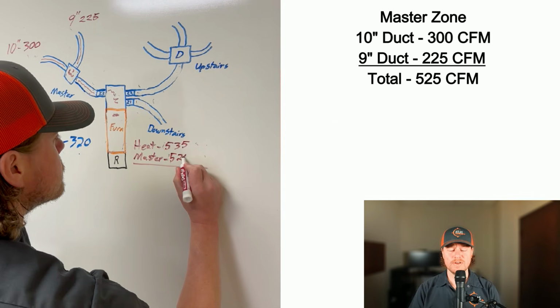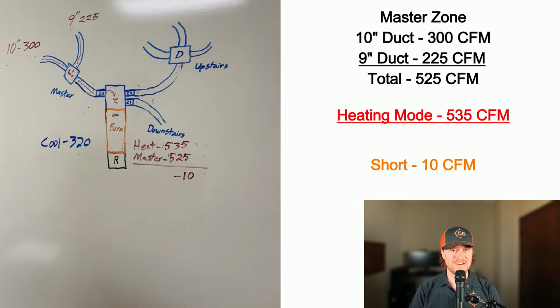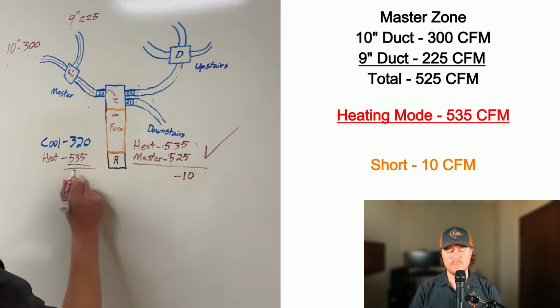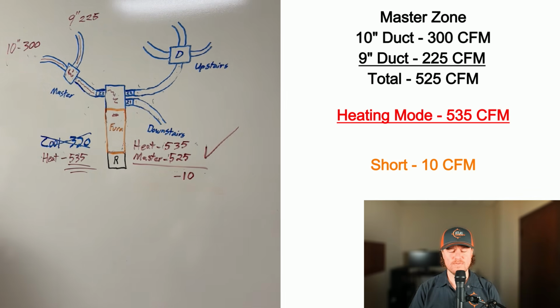Even though the outdoor unit can operate lower than that, the furnace cannot. This is highly dependent on which furnace you use as well. If you end up using a higher output furnace, you might have to design for 35 to 40%.